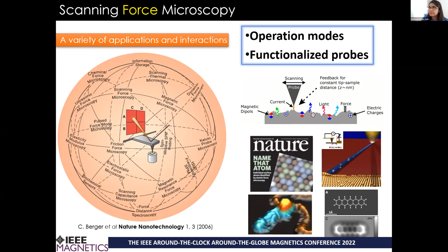The atomic force microscope, instead of using the quantum mechanical effect of tunneling, uses the atomic forces to map the tip-sample interaction. We need a cantilever with a very sharp tip at the end, and most of the AFM systems use a laser beam deflection setup. The AFM has a feedback loop using this laser deflection to control the force and the tip position. As shown in this scheme, the laser is reflected from the back of the cantilever that includes the very sharp tip at the end. And as the tip interacts with the surface, the laser position on the photodetector is used as a feedback loop to track the surface for imaging and measuring.